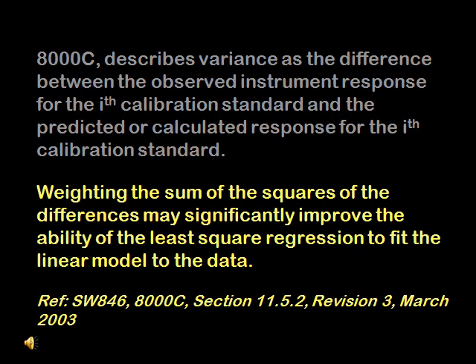If error is proportional to concentration or amount, a weighted regression should be used. The simplest form of weighted regression is RSD of calibration or response factors. If the physics of the measurement is understood, or if history has shown that a weighted or unweighted regression should be used, any change from weighted to unweighted and vice versa should be scrutinized and understood.